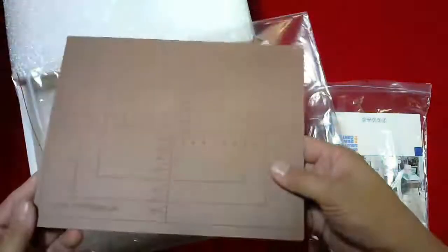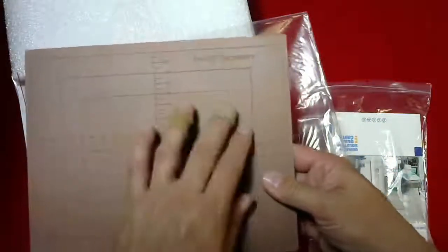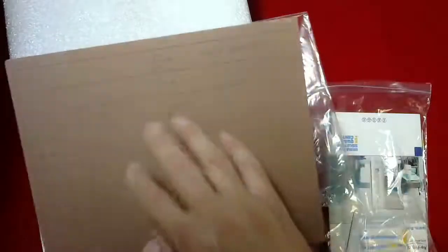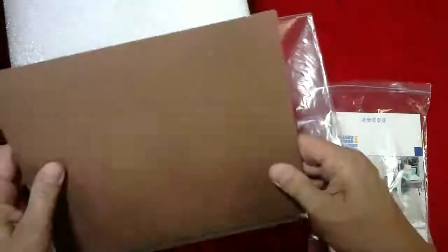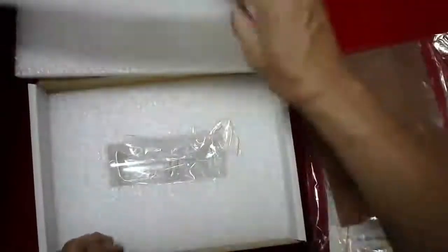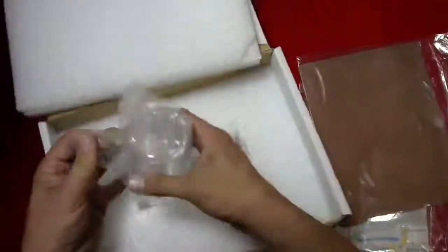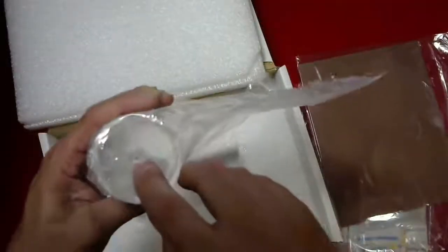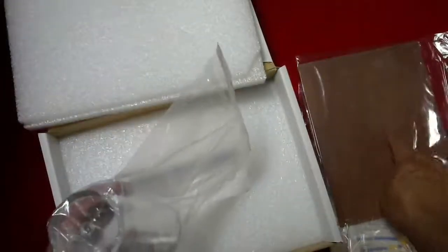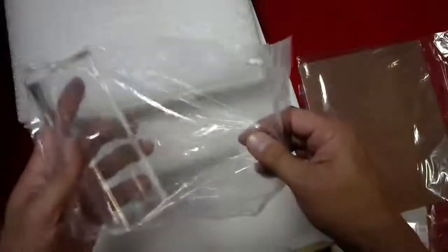This is a beam alignment test tool. So this is for checking the light field coincidence between the x-ray light and the actual measured radiation on the image. So that is a plate. And it also comes with a cylinder. This is for beam alignment. It has a BB here, and this gets placed on top of the beam alignment test tool.